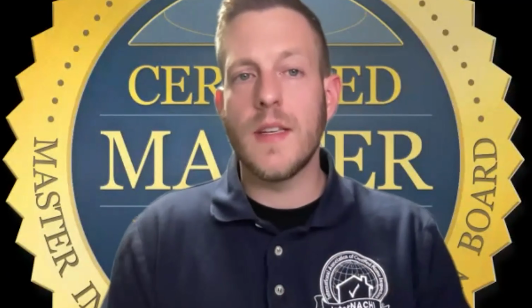Wayne asks, do I report on low voltage? Yes, I'm glad you mentioned that. I didn't have it pulled up, but for some reason here recently, I have been seeing doorbell transformers inside of electrical panels more often than not. Now, you cannot have that. Per the National Electric Code, it is a code violation to have a low voltage system next to a high voltage system. So that's something you would write up, that the doorbell transformer would need to be moved to the outside of the panel or relocated.